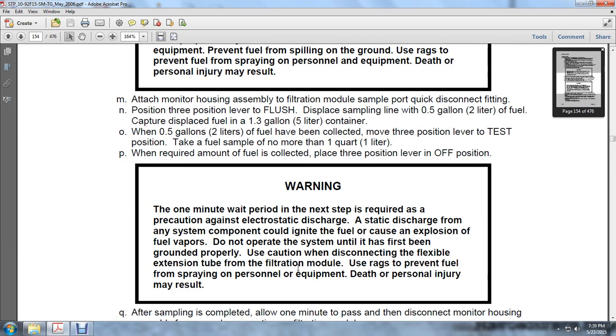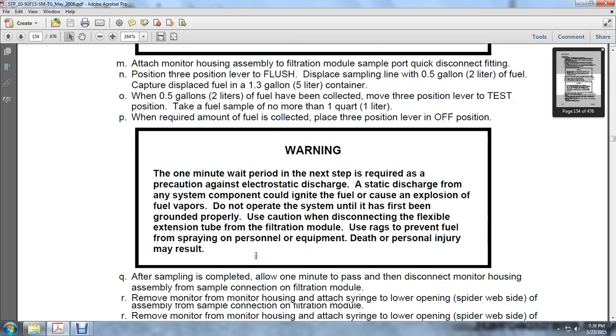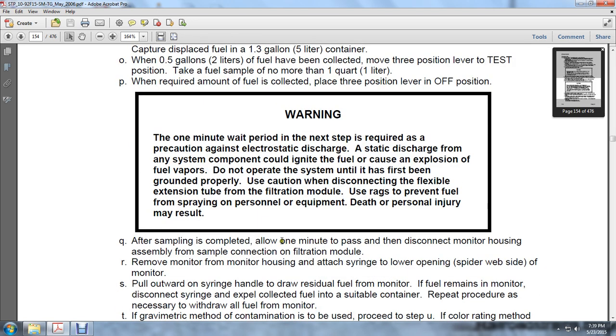The 1 minute wait period in the next step is required as a precaution against electrostatic charge. Static discharge from any system component could ignite the fuel vapors, causing an explosion. Do not operate the system until it has first been properly grounded. Use caution in disconnecting the flexible extension tube from the filtration module. Use rags to prevent spraying personnel or equipment. Death or personnel injury may result. After sampling is completed, allow 1 minute to pass, then disconnect the monitoring housing assembly from the sample connection on the filtration module.